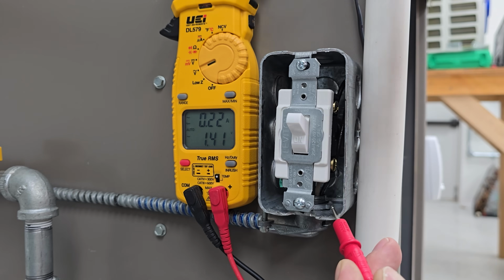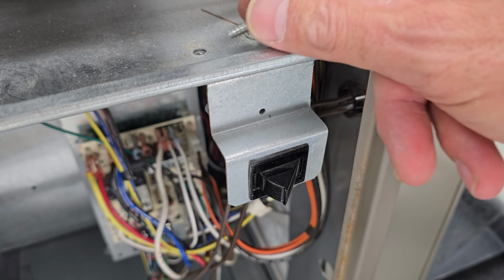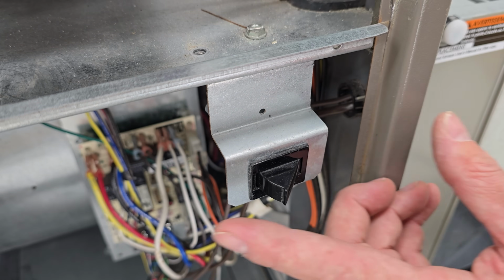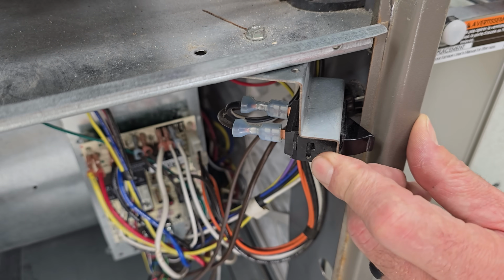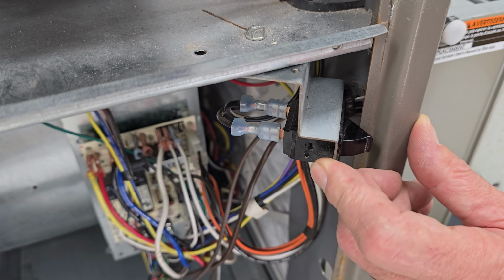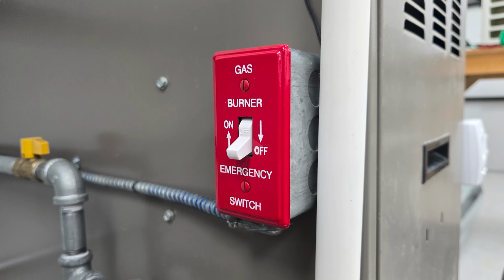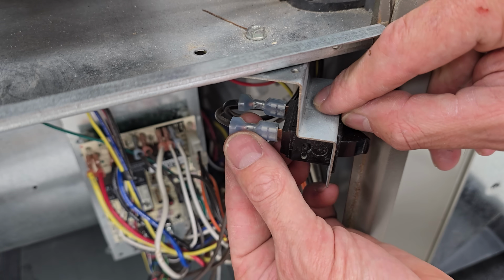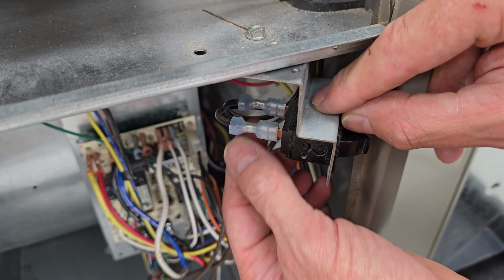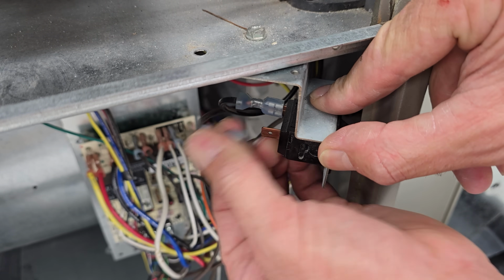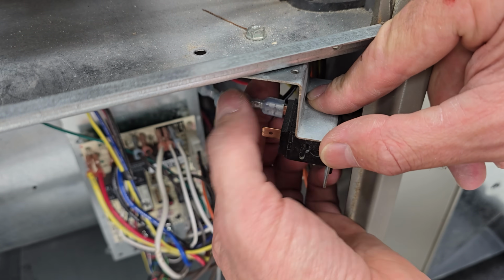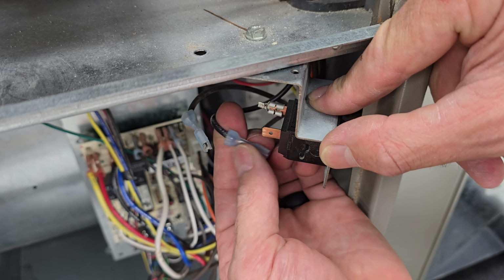And so we need to go ahead and see why, or where that's located. So we remove this one screw from the top right here, and we're just going to turn this so we can see this. And we have turned the emergency power switch to the off position. And so basically our problem is between these 2 terminals and that switch over there in the front. And so this wire is good, and here's our issue.